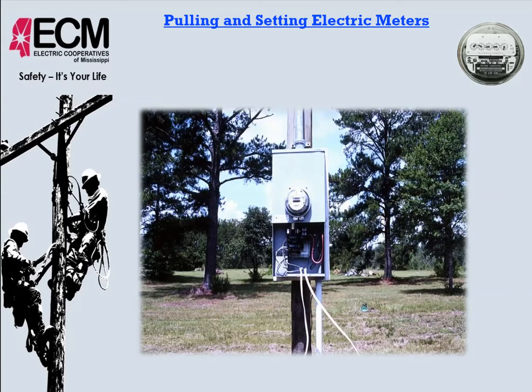Okay. Here's a meter base that we definitely would turn down. There's lots of issues here with this meter base. One, they've taken their cover off, leaving all this exposed, and then you have this Romex that is not connected, nor is it in conduit. Okay, it needs to be in conduit. If it's exposed, someone could be injured on that. And then also, this meter is turned upside down. It's an old analog meter. There's the wheel that turns, numbers of the dials, that should be on top, wheel on the bottom, so this meter's upside down. So probably they're stealing electricity.